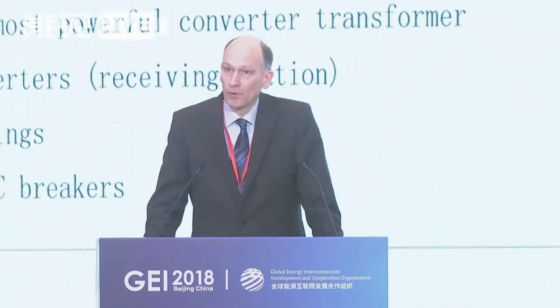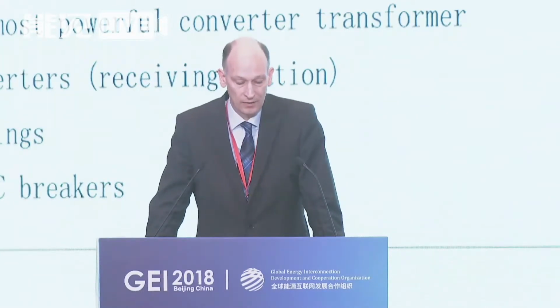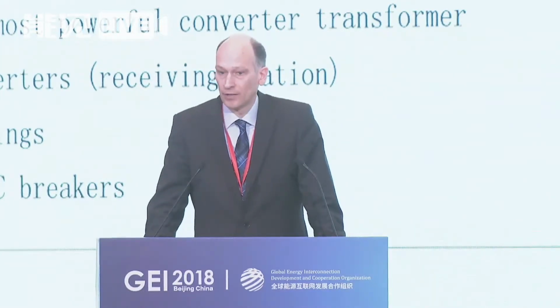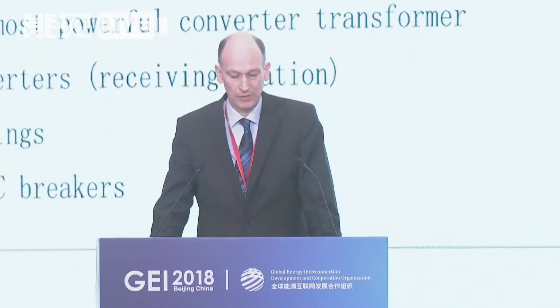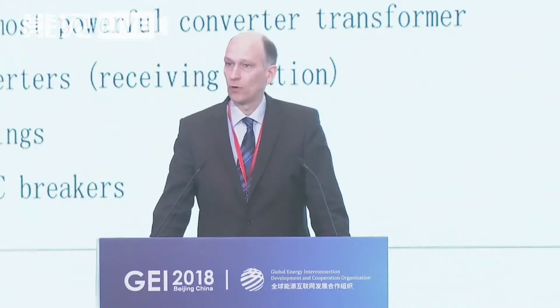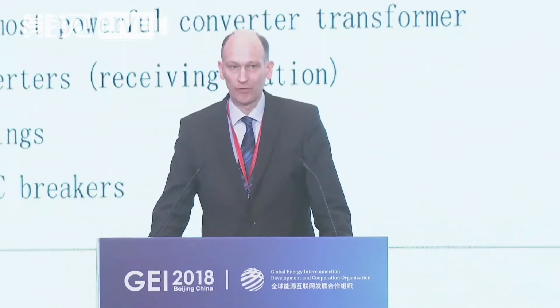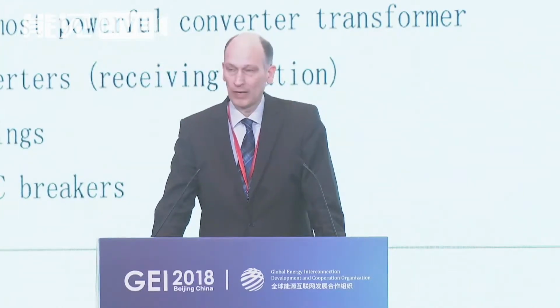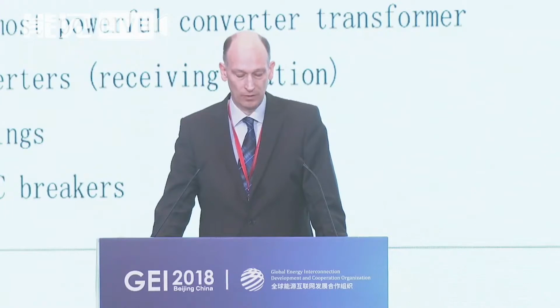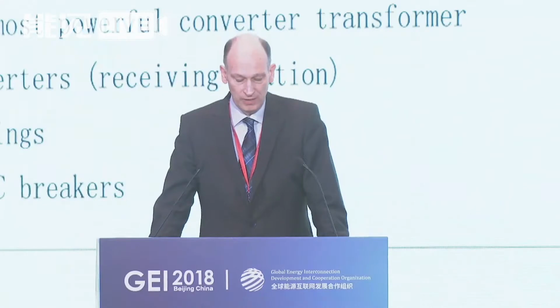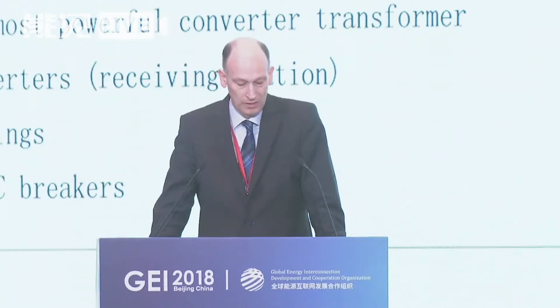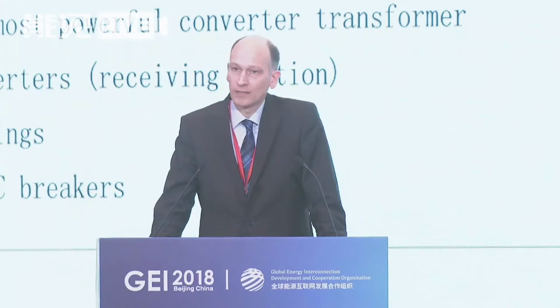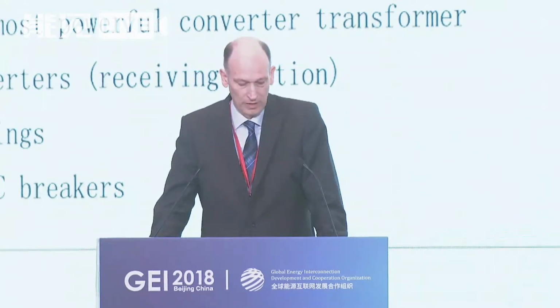Five months ago, in November 2017, together again with our colleagues and partners from State Grid, we had the successful type testing in Ludvika. The final transformer has a weight of 100 tons, a length of more than 30 meters, and a power rating of more than 600 MVA, connected to the 750 kV AC on the line side. This is really a historical breakthrough within HVDC high power long distance transmission lines, and due to excellent collaboration with our partners from State Grid we could achieve all timelines.